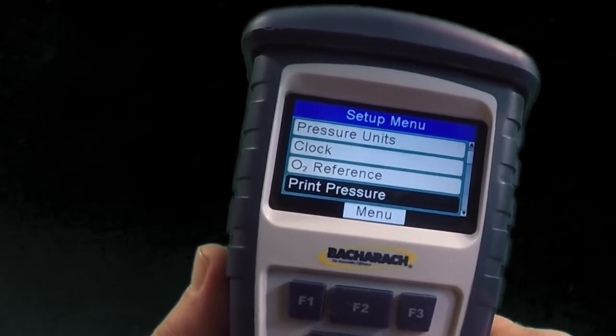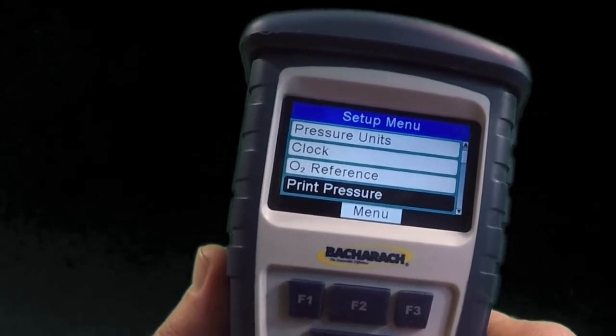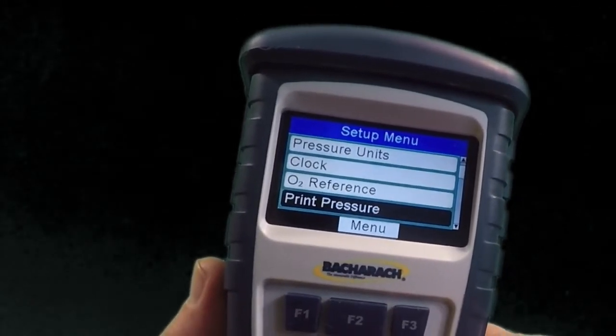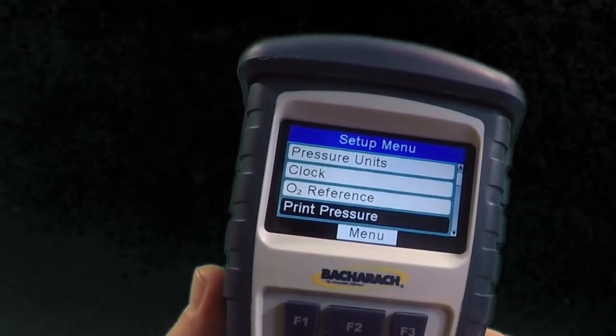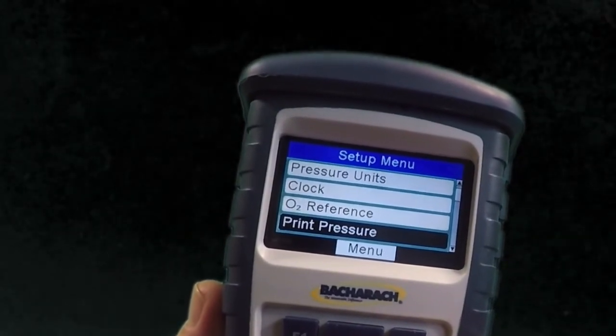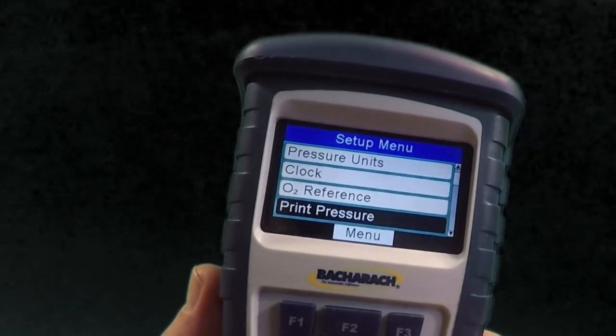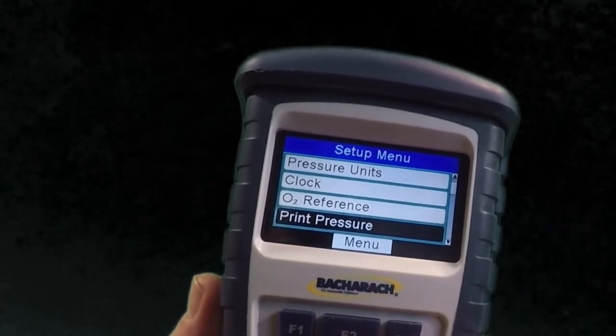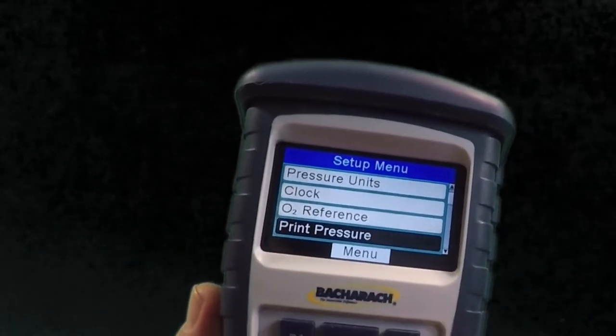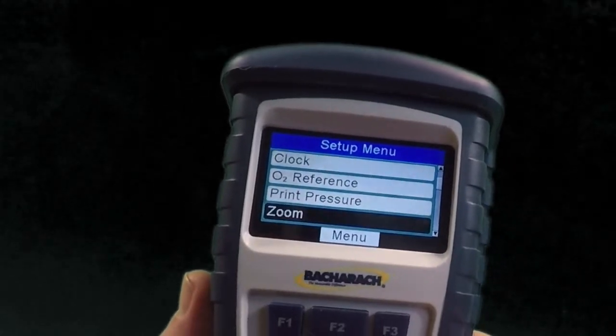Okay, so we're going to go down one more, hit print pressure. Print pressure determines whether the pressure reading is included on the thermal paper printout. Generally, I would select no, as combustion readings are rarely taken in the same place as the draft readings. Just depends on the equipment being tested.